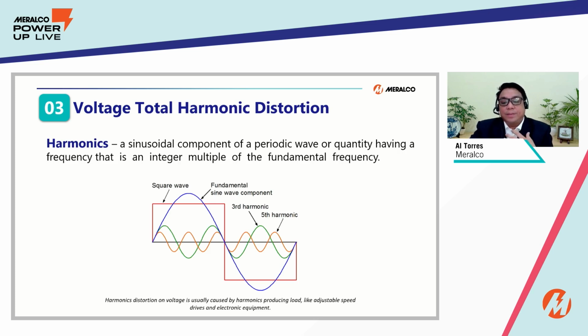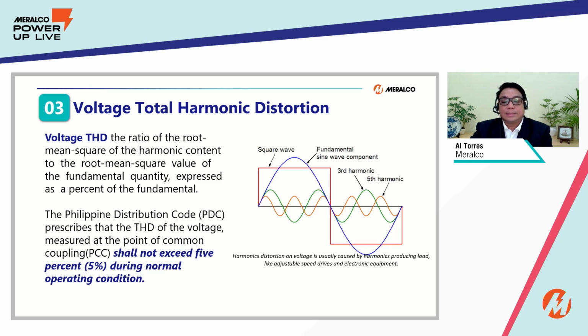Next is harmonic problem. Harmonic problems are waveform distortion brought about by nonlinear loads, such as variable frequency drives, uninterruptible power supplies, and computer power supplies. Based on the Philippine Distribution Code, the prescribed limit for voltage total harmonic distortion is 5%.